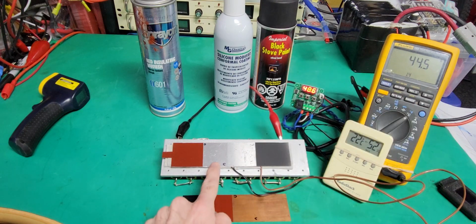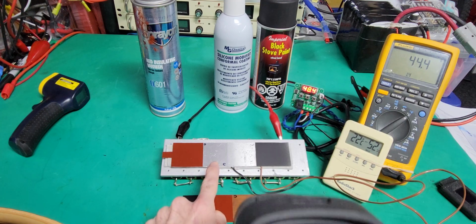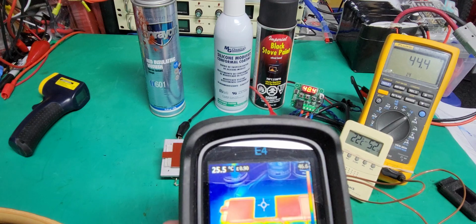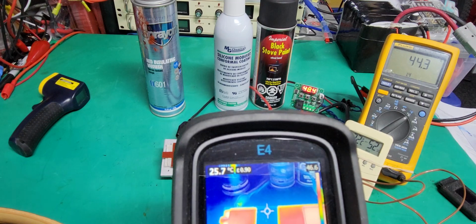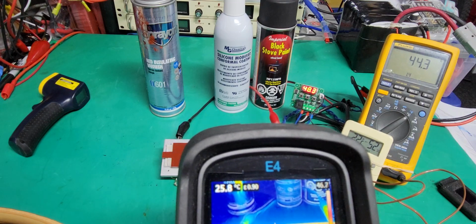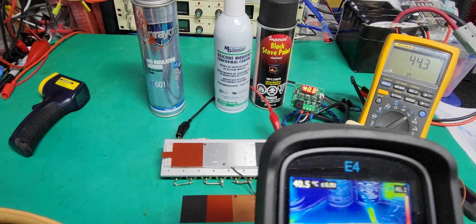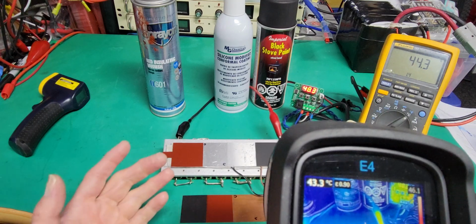If it's an emissivity of aluminum like that, and you know aluminum is typically between 0.1 and 0.2, which is very poor, you will not get the right reading. And this is exactly what we see here. We see 25 degrees Celsius instead of like 40 or 45. So that's a big difference.